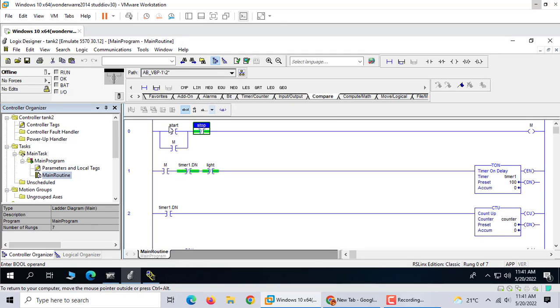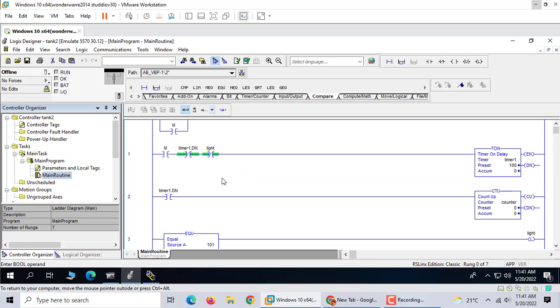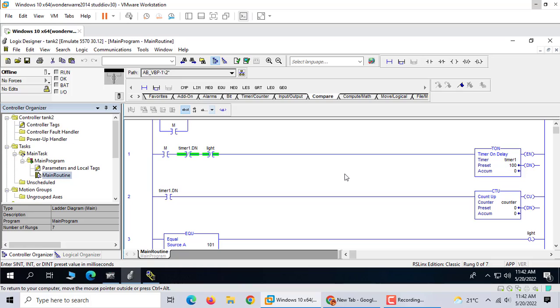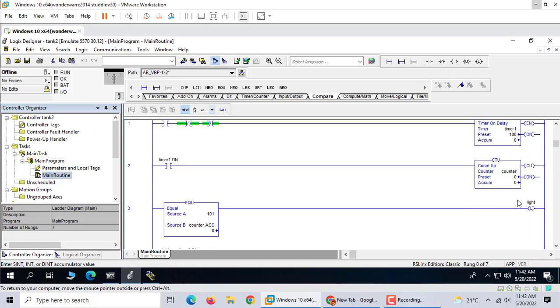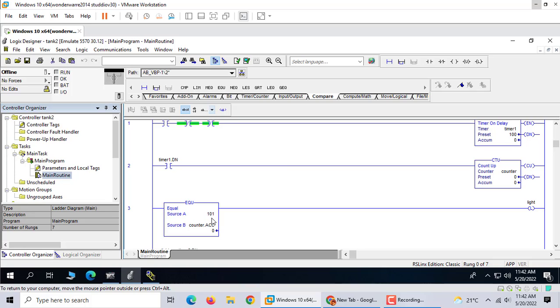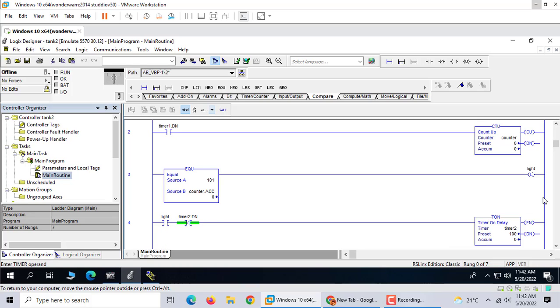So we start and stop to make M active. Then timer 1 is on. Every 100 milliseconds it times. When it's done, it counts up. If the counter is active and the accumulator equals 100, then the light is on.